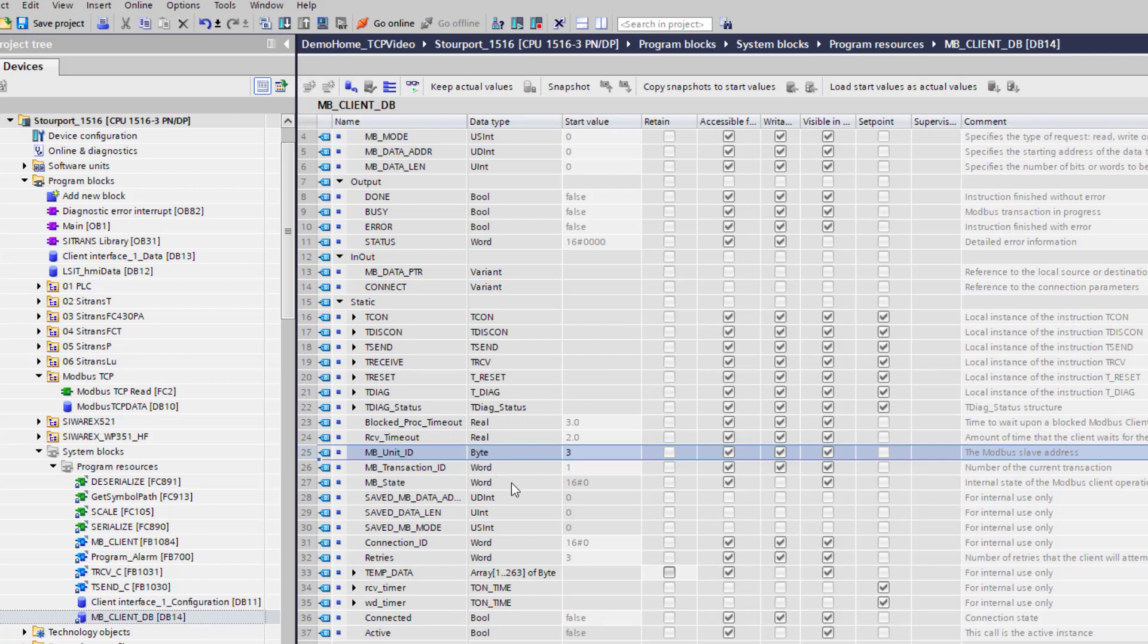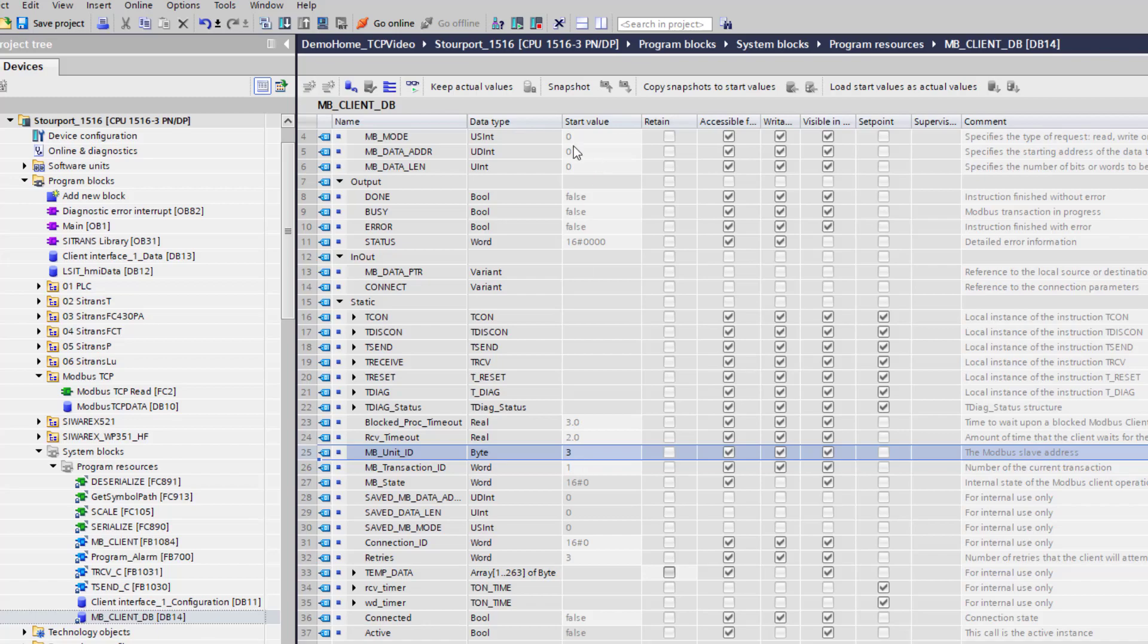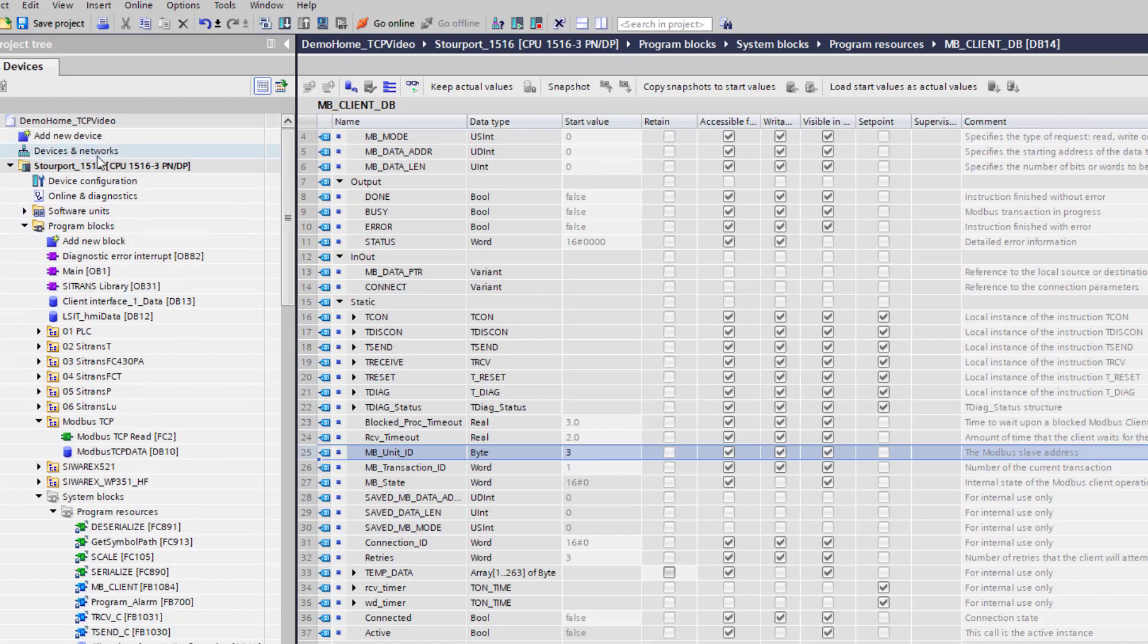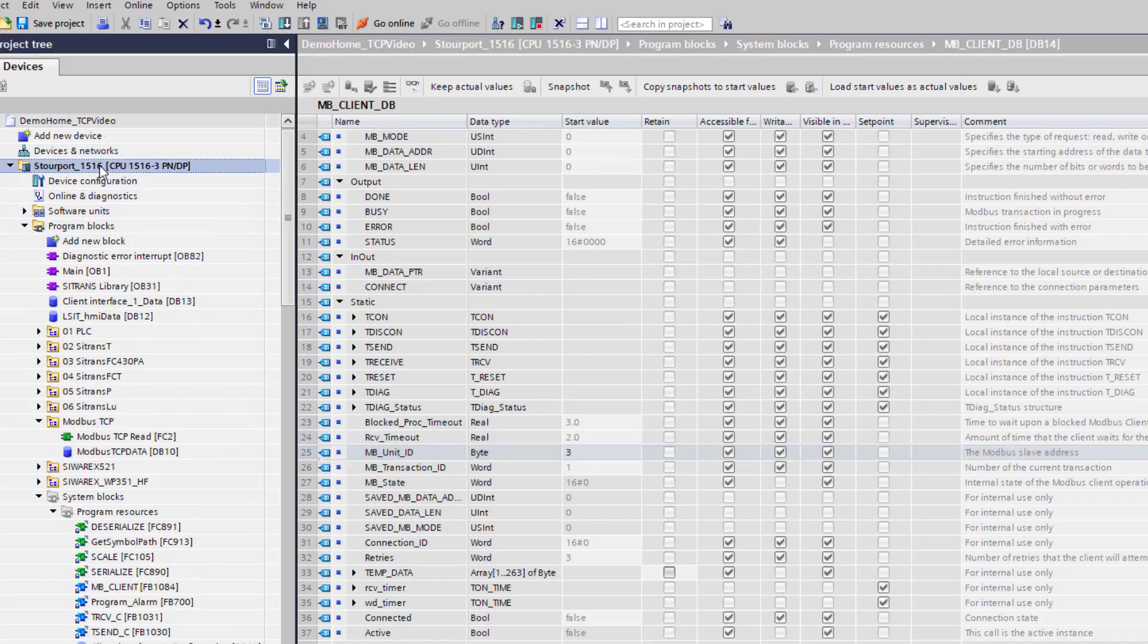MB unit ID. This is the Modbus address of the 485 slave. You can see over here, it all makes sense when you know where to look for it. And I have recorded this video to save you two hours trying to find it. So you need to change that to match the slave that you are connecting to. So all that remains to be done now is that we need to compile and download that.